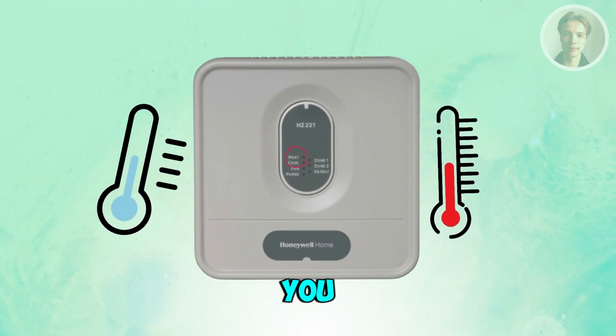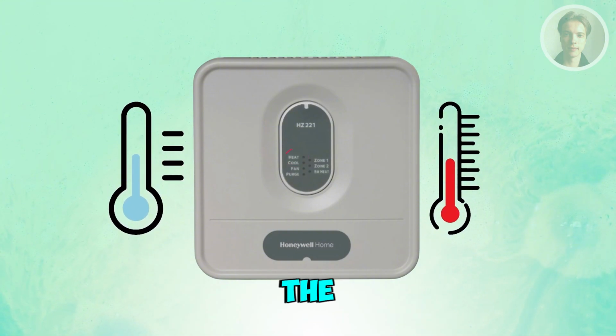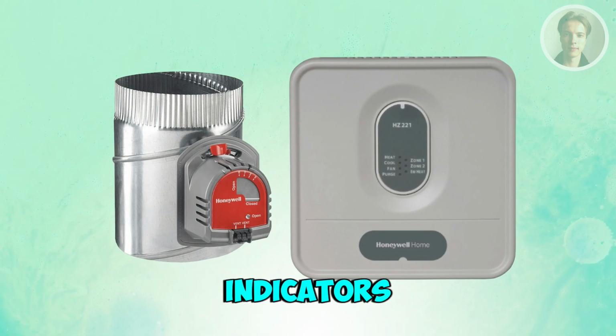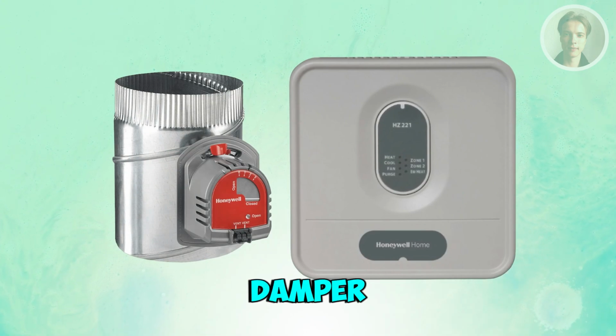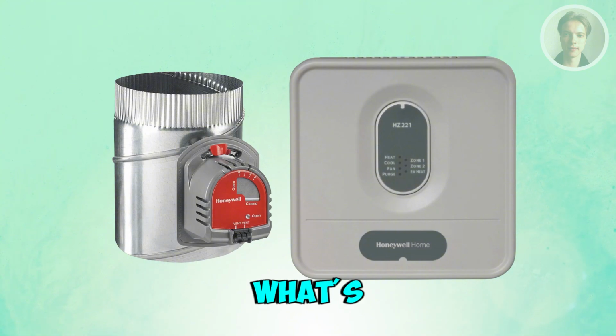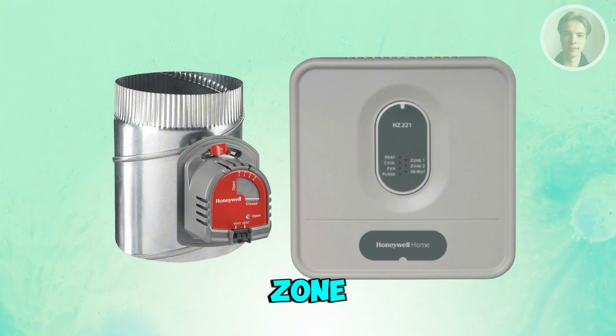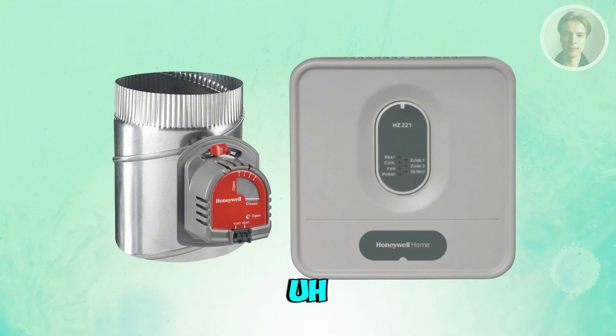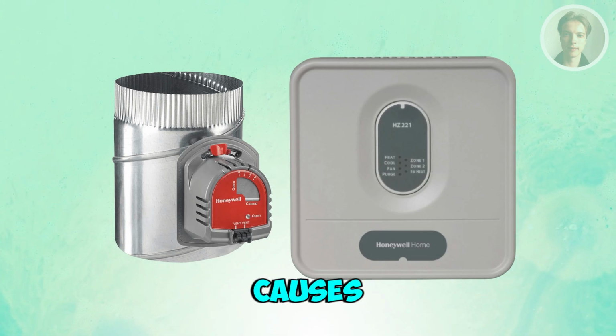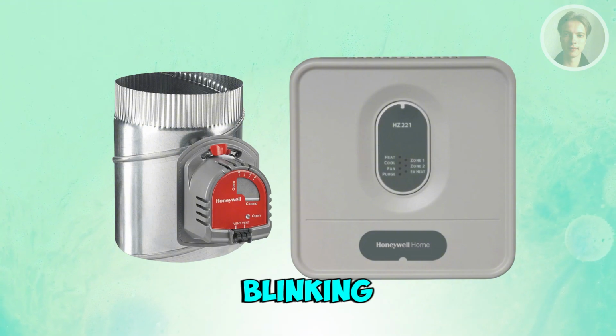Now, also, you may want to closely look at the damper LEDs and zone indicators. Now, a TrueZone panel's damper lights tell you what's happening behind the scenes. Now, if a zone keeps flashing, the dampers may be stuck, miswired, or not reaching the end position, which causes the board to cause the blinking.